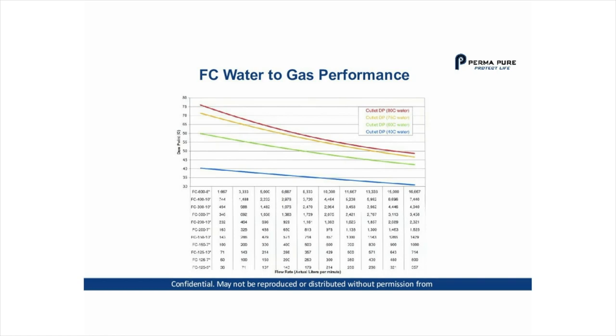The FC series can also be used for water-to-gas, and the FC water-to-gas performance chart works the same way as the MH performance curve: you pick the outlet dew point you need, and depending on the water temperature you are using, you read the outlet dew point off the curve.